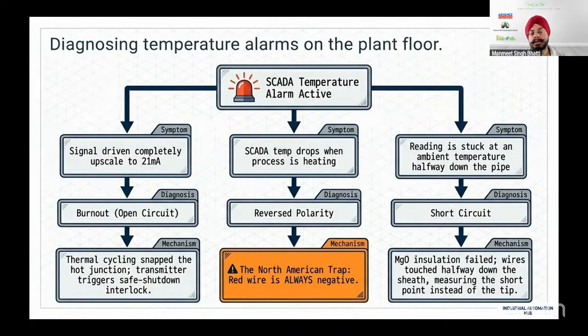Now, this is something where people do not have much clarity. On the SCADA, you see that a temperature alarm is active. There could be many, many reasons. First of all, the first reason is that your milliampere has gone to 21 milliampere. We covered milliampere signals last week. So 21 milliampere means that an open circuit is there. So your circuit has already burnt out. You have got a higher reading.